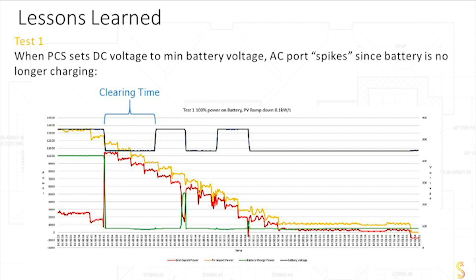So the voltage, after a few moments, actually turns back on. The voltage jumps up. That's why you see kind of this valley and then a peak on the voltage line, because the inverter actually sees the red line is far above zero and turns the battery back on. It says, hey, you're okay to turn back on. So it turns the battery on. And after waiting for another period in time, the battery just kind of waits. It checks to see everything's up to snuff and into spec. And so it sits there, and after a certain amount of time, it says, okay, I'm ready to charge. You gave me my voltage back. The red line's above the zero, and I'm going to go ahead and charge again if I need to.